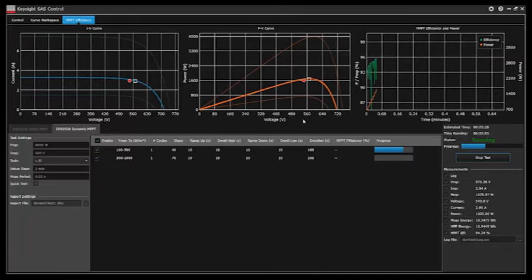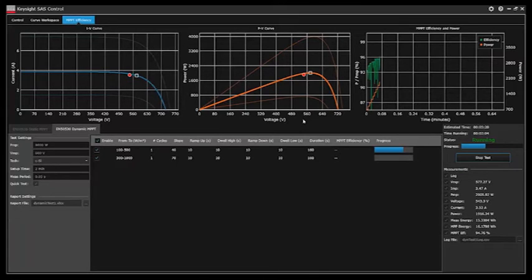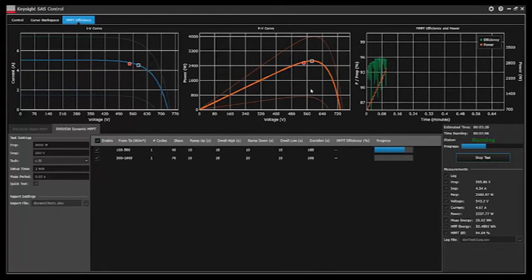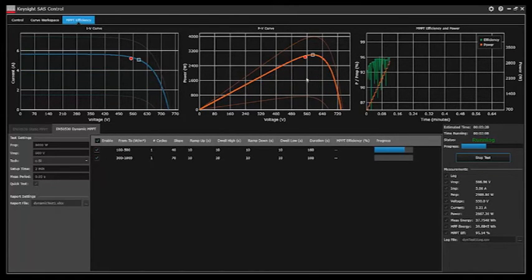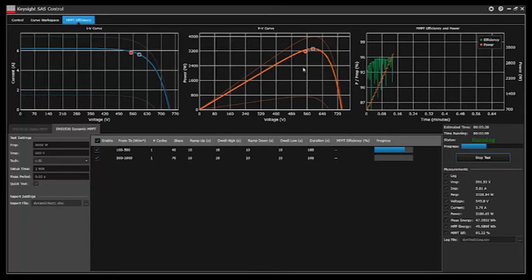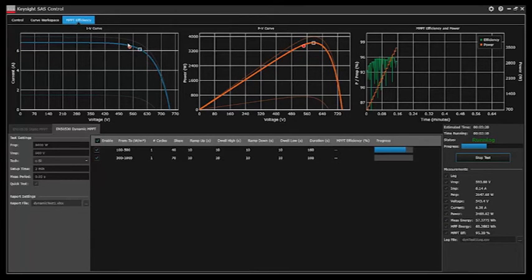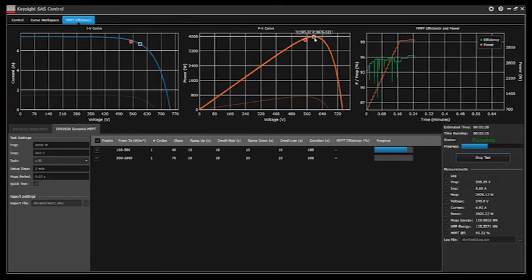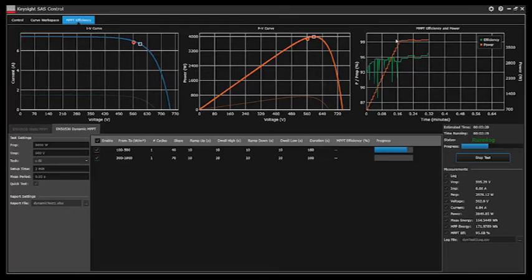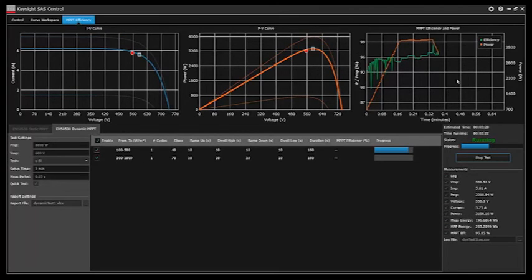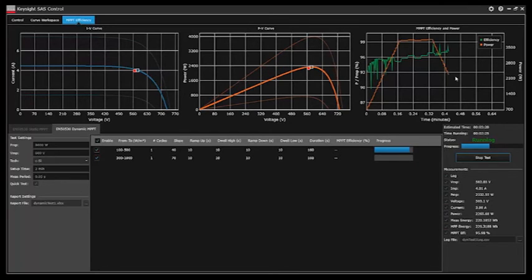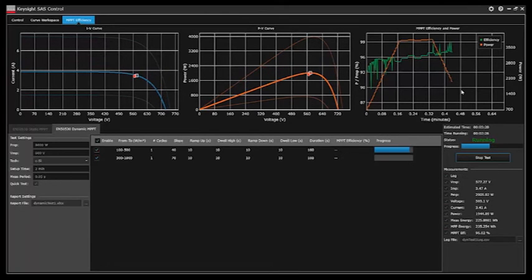Now that we've let our solar array inverter settle you can see that we're ramping up different irradiances and showing you real time IV curves and PV curves with the corresponding operating points and maximum power points. Here on the right graph you'll see that we're graphing MPPT efficiency as well as the power over time. This gives you some pretty good insight into how your test is running.